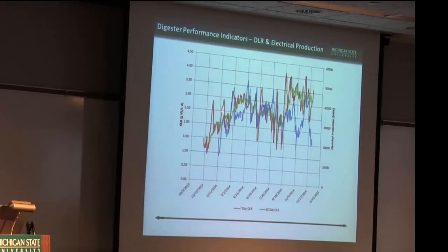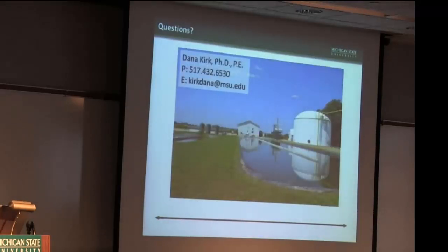We did run into a nice, steady, relatively smooth range there through the summer months. And then we've had some mechanical issues with our combined heat and power unit that have caused us to be down, especially quite a bit in November. So just another trending pattern that we're looking at for the year.